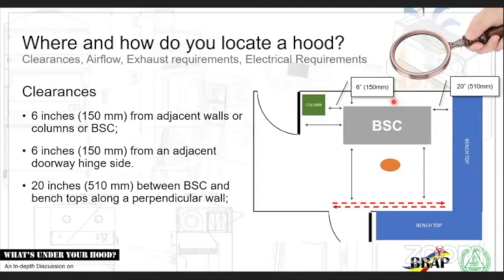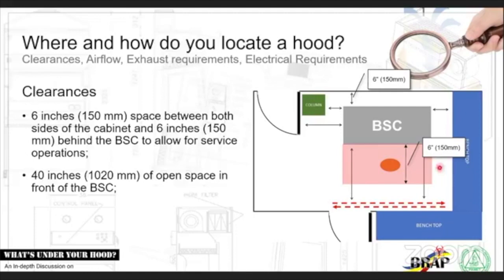Now, the 6 inches on this side and at the back is just the space for you, or for your engineers, to be able to manipulate the equipment if ever they need to service it. So, 6 inches back from the back. Now we have your work area in the front. This is where you actually put yourself in. This is an imaginary area in the front of your biosafety cabinet. This should be 40 inches or approximately 1 meter. That's for you.